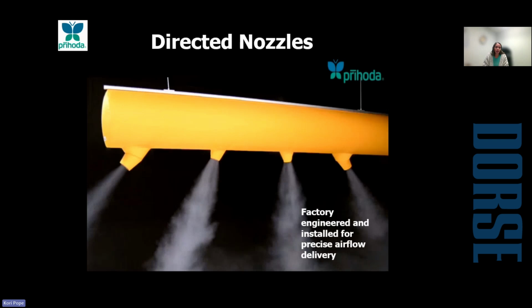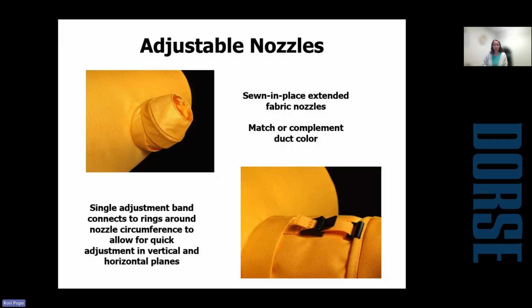So we have another variation of our large nozzle that we call our directed nozzle. This just comes at a pre-manufactured degree from production. And then we have another variation of our large nozzle called our adjustable nozzle. This is a 100% adjustable nozzle from the damper to actually where that air is blowing. So once you get it on site, it'll have 3 of these bands here, one at the top and then one at the left and right, where you can actually pull it and adjust where that air is going to be blowing.